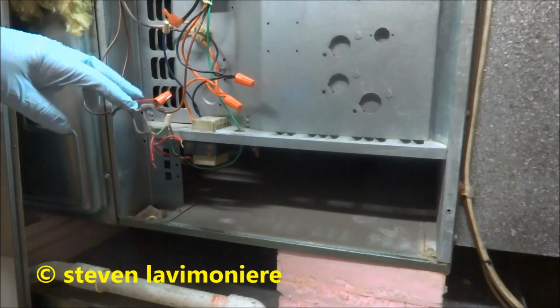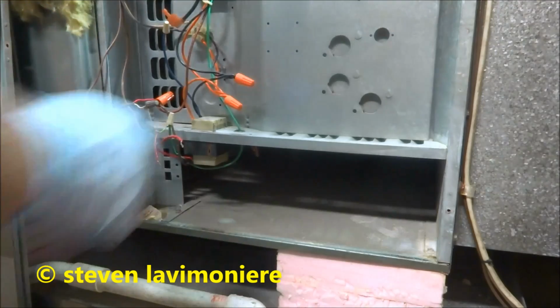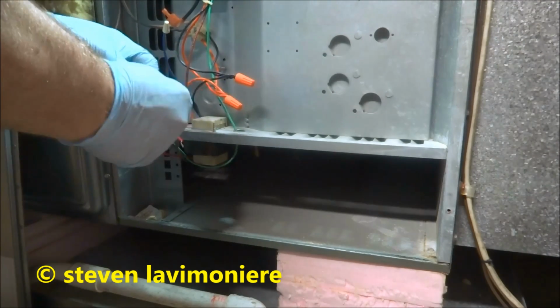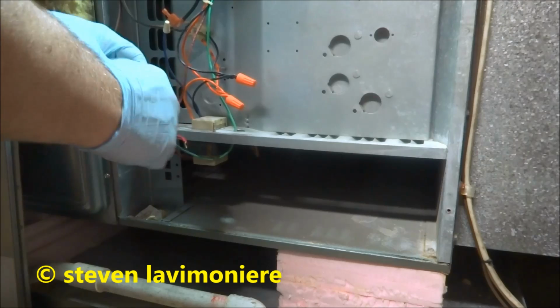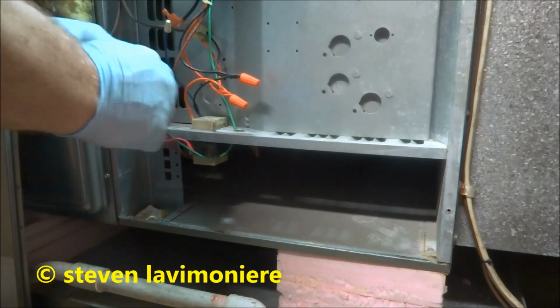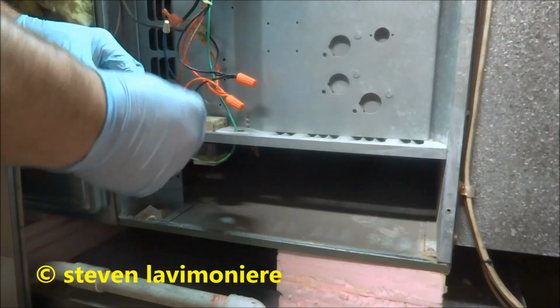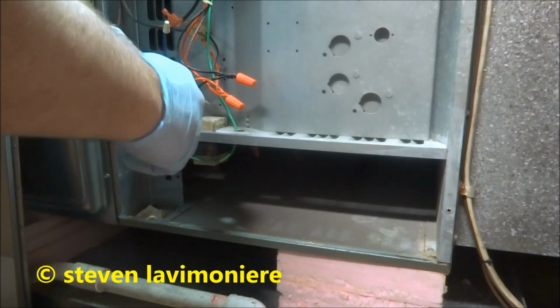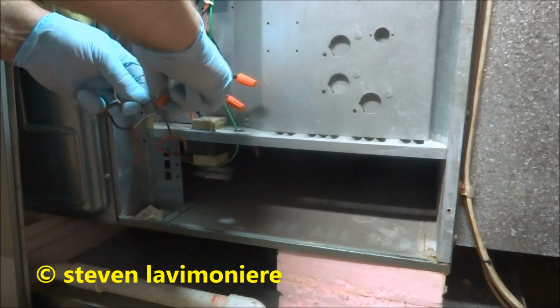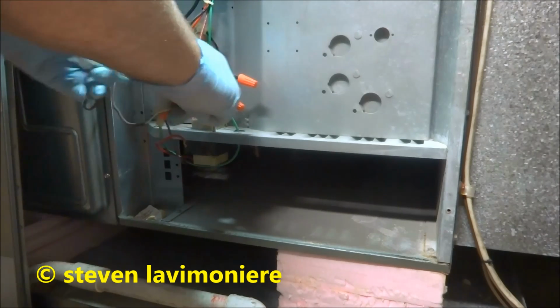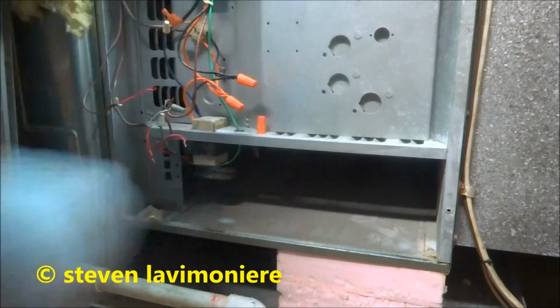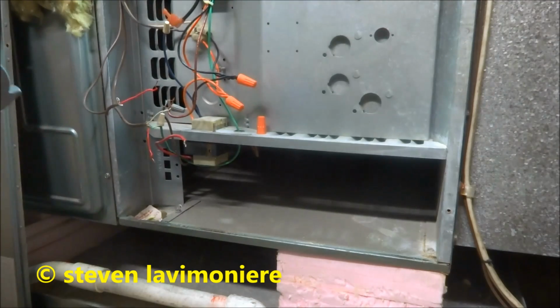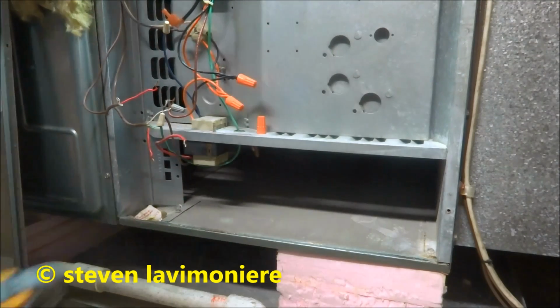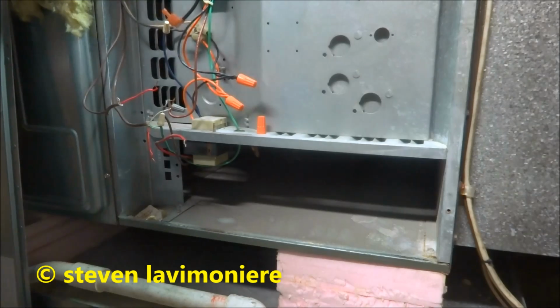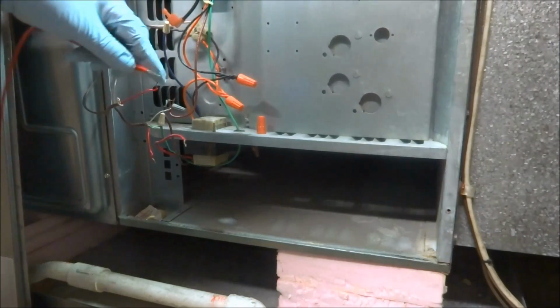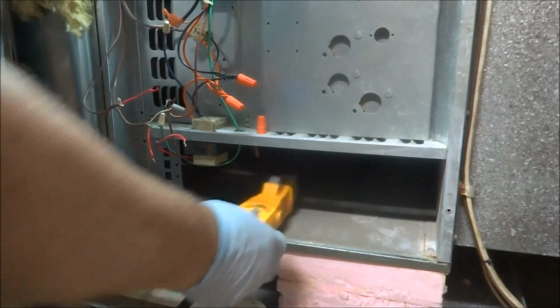I am going to check this before I hook it up. Make sure it's okay. Check it for low ohms. Might have a short somewhere. I want to check it. I'm going to check this for having a short. Low ohms. We'll check the ohms. That goes out to the contactor, because that would definitely fry my unit. Let's see what we got for ohms here.